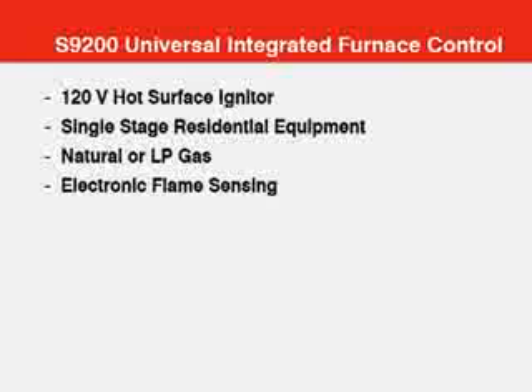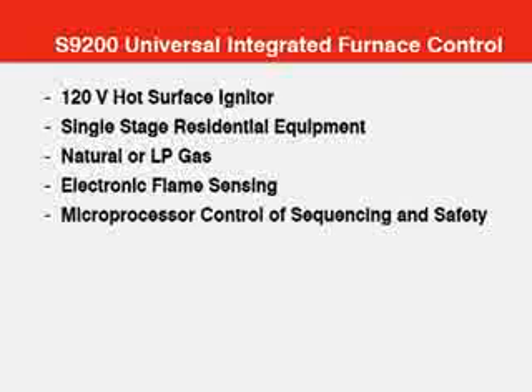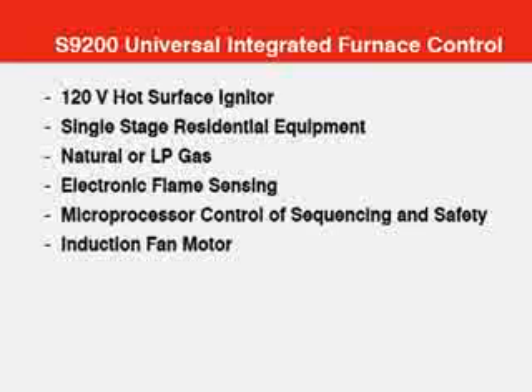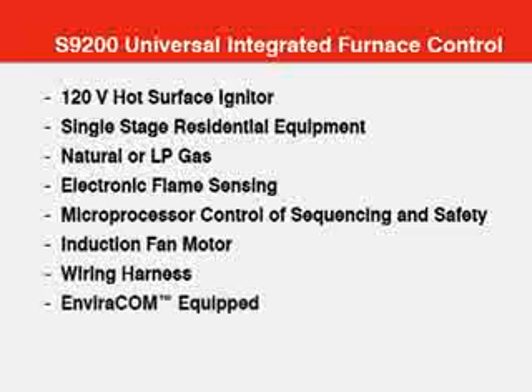It uses electronic flame rectification to monitor the burner flame. The heart of the device is a microprocessor that controls all safety and sequencing operations. It monitors the air-proving switch, the high limit, and rollout switches. It controls a standard induction-type multi-speed fan motor. Wiring adapters are included to make the electrical connections to most furnaces. For advanced systems, it has the EnviraCOM communication capability to enable reporting system status, diagnostics, troubleshooting information, and HVAC system control. LEDs on the board show system status, performance, and diagnostic information.